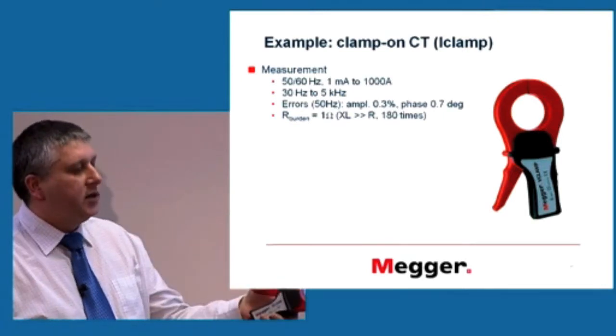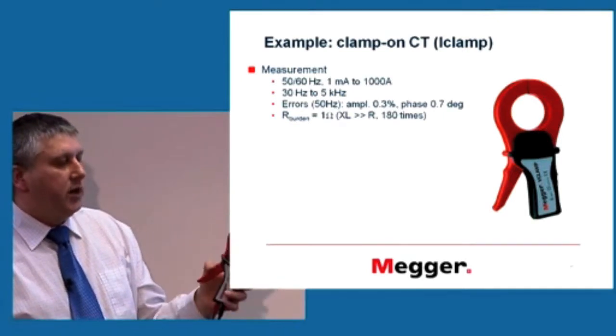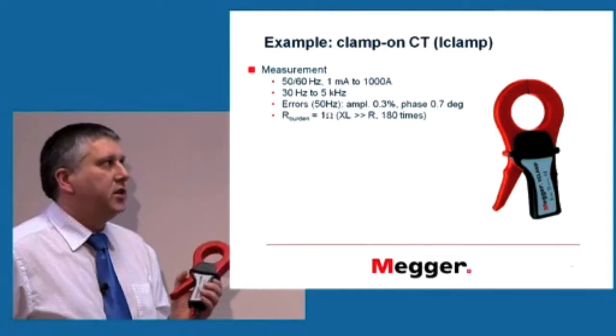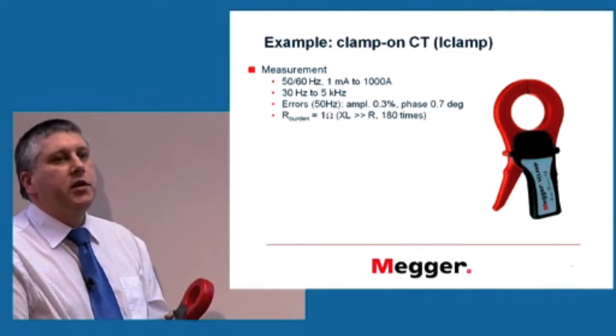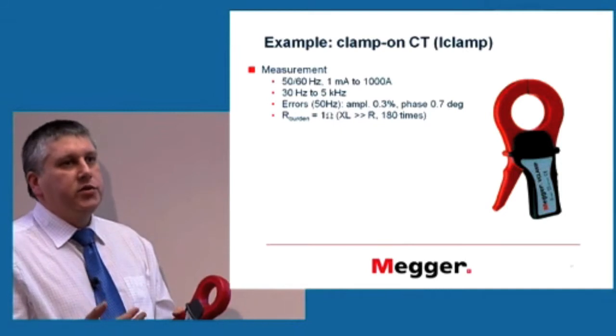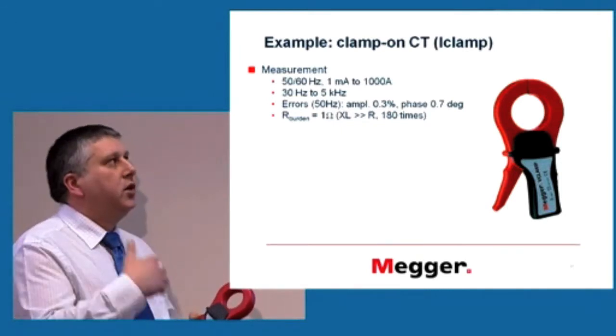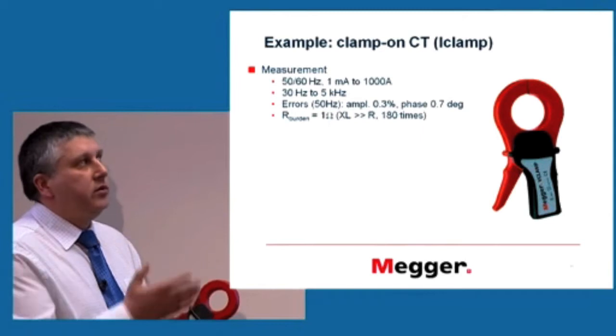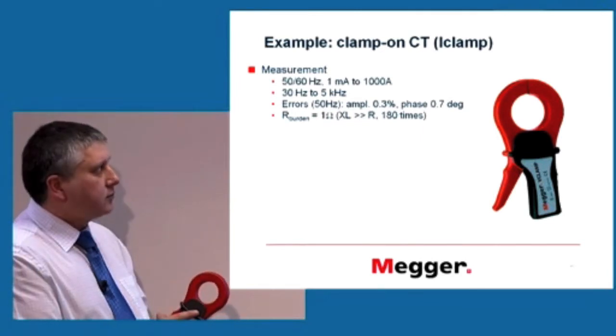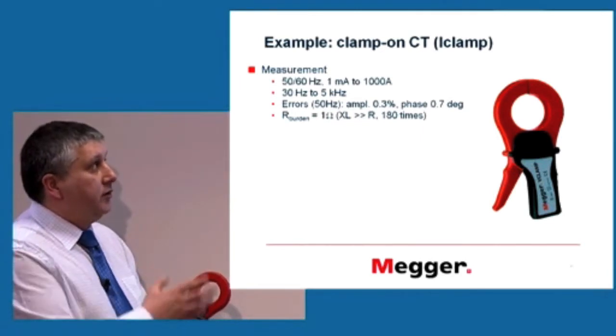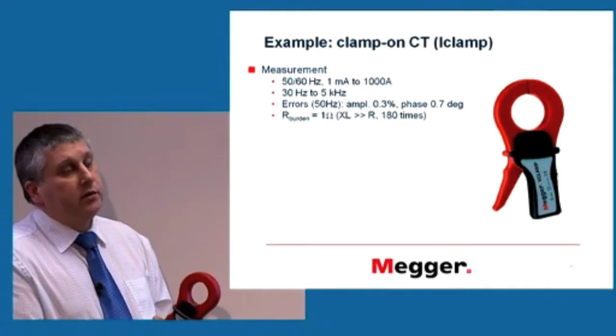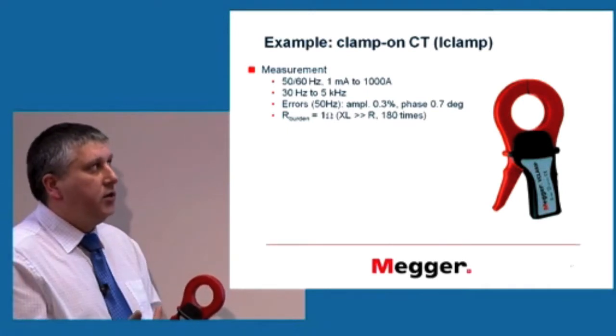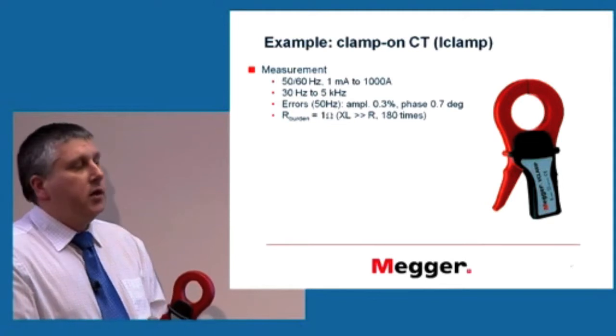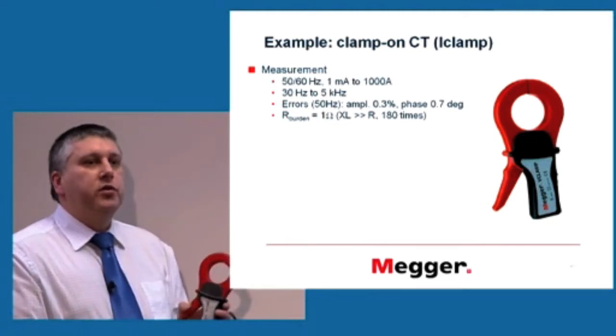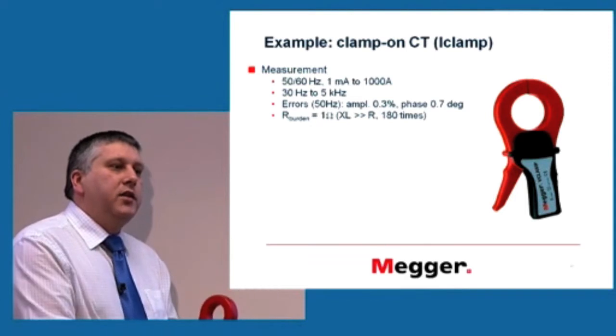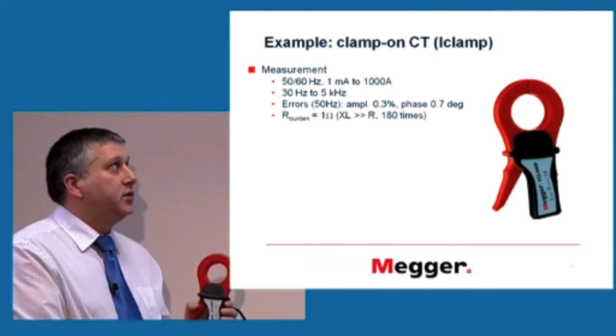This can be clamped around a 1,000 amp 50 hertz conductor, and it will allow us to measure that current quite correctly. The ratio is 1,000, or 1 to 1,000, so it steps it down 1,000 times. Hence, the current at the secondary will be 1 amp for 1,000 amps. The errors for the full range are 0.3% of the current value and 0.7 degree of the phase shift, and these are used for power quality and energy metering as well in some cases.